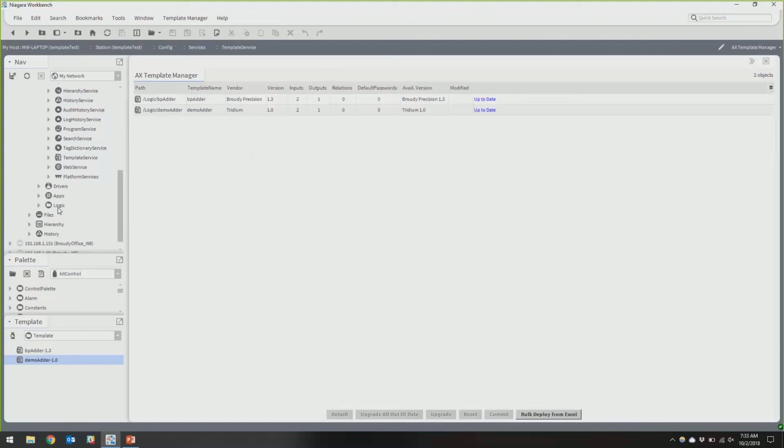But there's also things, we had the same problem with CFM control. You know, we had units that were trying to maintain 60,000 CFM as a static set point. It wasn't a very dynamic set point. So the set point stayed pretty much at 55,000 CFM. Our CFMs, however, because of the airflow stations we were using, it was on a fan array, so they were unstable. And it was causing exactly the same thing on our drives.